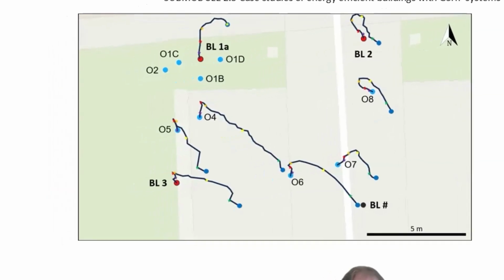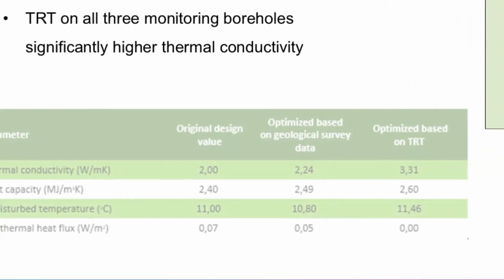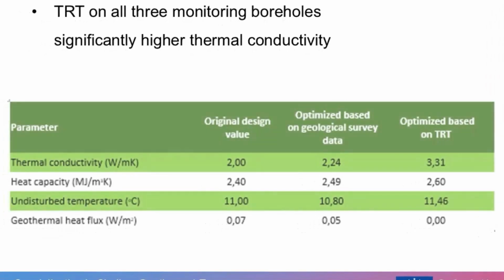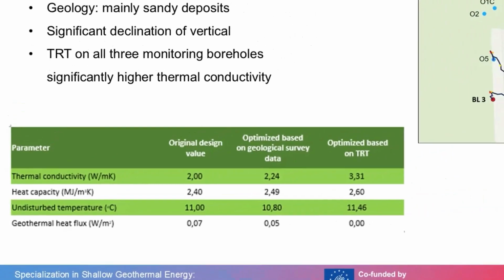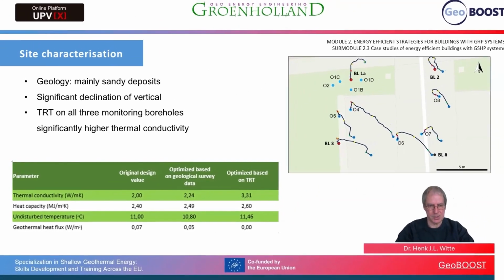Also, we did a thermal response test on all 3 boreholes that we are going to monitor. And what we can see in a little table is that for the thermal conductivity, the original design value was 2. If we base a calculation on detailed geological data, we get a thermal conductivity of 2.24. But if we do the actual measurements with the thermal response test, we find 3.3. Very much higher. This is an indication of limitations of the available data, because in this case in Groningen, the sands are actually quite overcompacted due to cover in the previous ice age. And that causes better contact between the sand particles and therefore a higher thermal conductivity not found in other parts of the Netherlands.